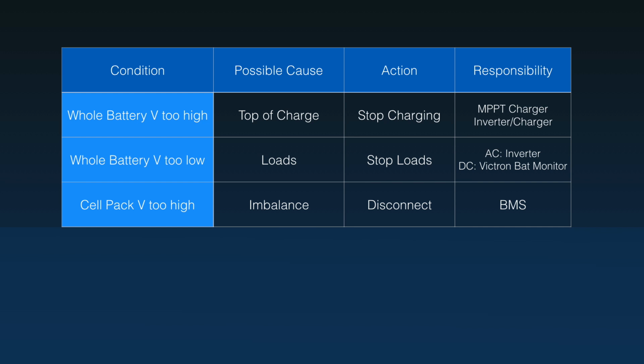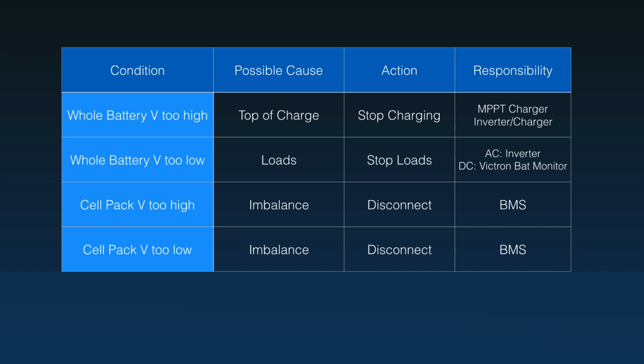In our situation, we're probably just going to disconnect the battery completely if we reach this situation, and same with the cells getting too low. Again, if we're stopping the loads when the voltage of the whole battery gets too low, we should never encounter this situation unless there's an imbalance issue or for some reason the loads don't stop. So the battery management system will handle those situations.